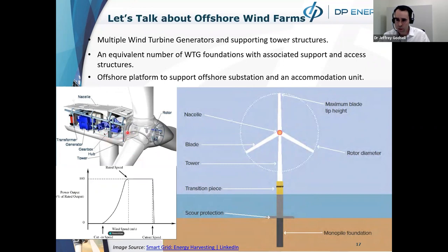Not all wind turbines have gearboxes. The vast majority of future offshore wind turbines are envisaged to move to what are called direct drive machines. The gearbox takes the rotation, which might be 10 or 15 RPM, and steps it up into the hundreds, sometimes over 1500 RPM, to feed a generator. The generator is then connected to a transformer. You can have power electronics, and the power is exported from the turbine down.